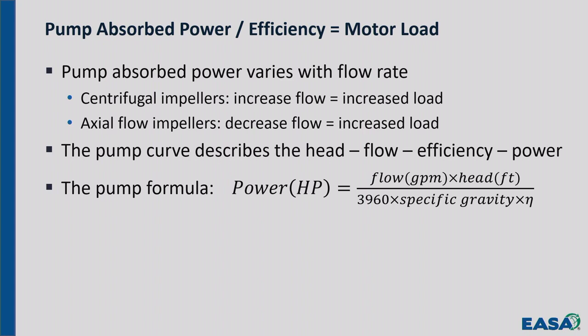Okay? Looks like I hit the button a couple times here. The pump curve describes how much power you need for a certain head and flow. Unlike electric motors, where you've got a certain amount of power and current and voltage, on the pump, those are variables. You can have a pump with higher flow, or you can close a valve and bring the flow down. The head can go up, the head can go down, and the power required will vary as that head and flow change. So that's different than an electric motor, and it's described in what we call the pump curve.